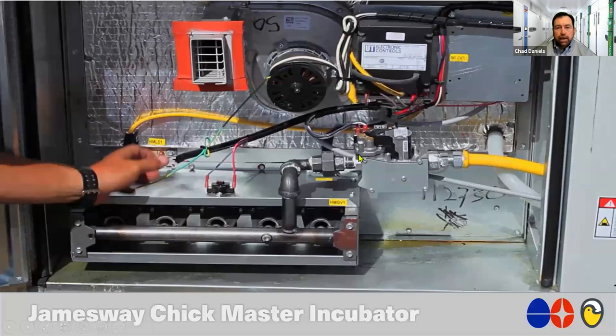Here's our main gas valve. It also has a small bypass for a pilot. So it'll send a little bit of gas to the main combustion heat exchanger so it can light the ignition. And then it's got a secondary stage that will kick on, and you get full combustion as long as everything works correctly. Here's our igniter. And this is our ignition tube that comes down to that combustion chamber. And then here's our combustion blower.